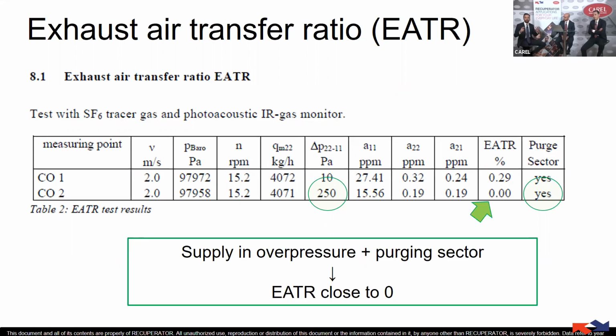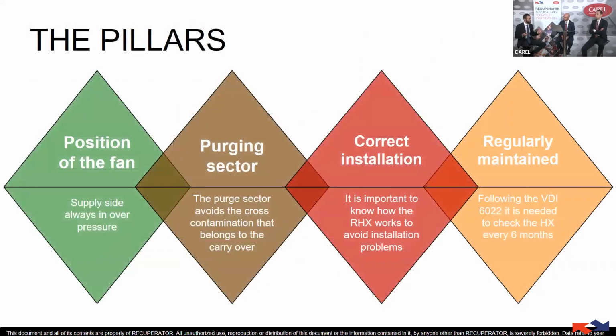Let's focus on 4 main pillars. The first one is the position of the fan. We have seen that the supply side should be in overpressure. The second one is to have the purging sector well installed and well designed, in the way we avoid the carryover. Then we need a correct installation, of course, because the manufacturer should know exactly how to install the rotary heat exchanger, knowing the purging sector. And then the last one is the maintenance. The maintenance is really important to keep the rotary heat exchanger running in a proper way.